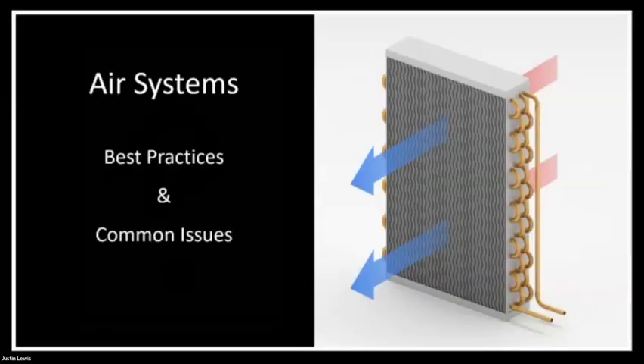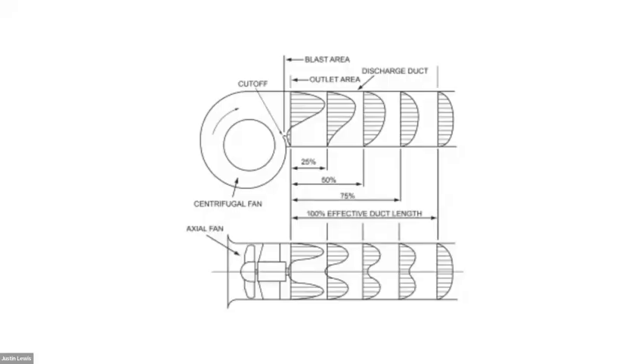So what are we talking about? What kind of things are we looking for in the accessibility review and the site walks? Let's look at air first. It's the TAB contractor's responsibility to not only know how to use their equipment, but to know when and where to use that equipment for accurate testing of the systems. A bad measurement is much worse than no measurement at all. We need to make sure that we can provide accurate and repeatable readings.